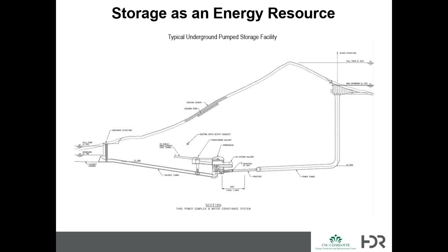And then there are three modes of operation: pumping, generating, and condensing. The way a pump turbine starts is in condensing mode, with what's called depressing air. You inject air into the runner chamber and push the water down in the draft tube, going to your Lake Jocassee lower reservoir, and you start the pump spinning in air. It's incredibly expensive to start the pump rotating in water with all that friction. So you start it spinning in air, you synchronize it, then you open the gates, and then you start pumping uphill.